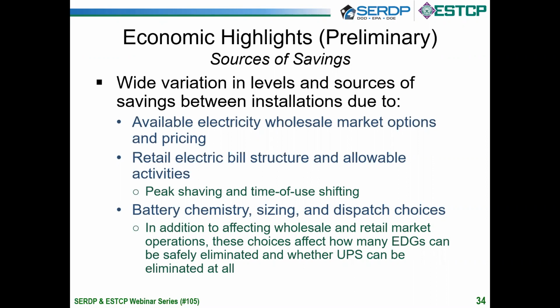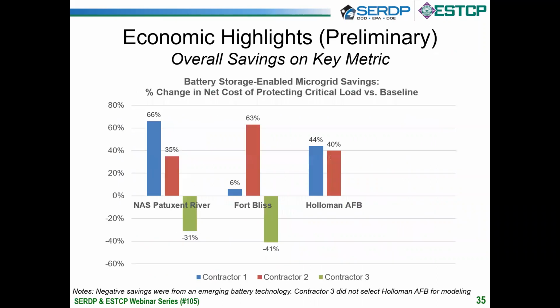$160,000 in capital costs per UPS and about $3,000 in annual O&M costs. That's for a 250 kVA, 15-minute UPS. When the battery system could perform the ride-through function itself, you could eliminate UPS and create annuity savings. Battery duration for all chemistries can affect if and how many diesel generators can be safely eliminated from the microgrid to achieve similar ongoing savings. So we'll go to slide 35, where we showed some economic results for a few of the installations.